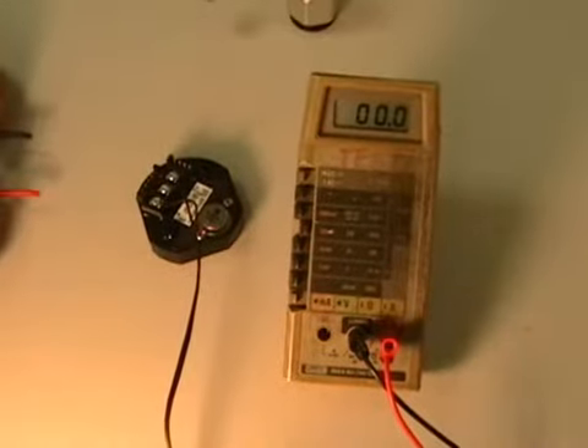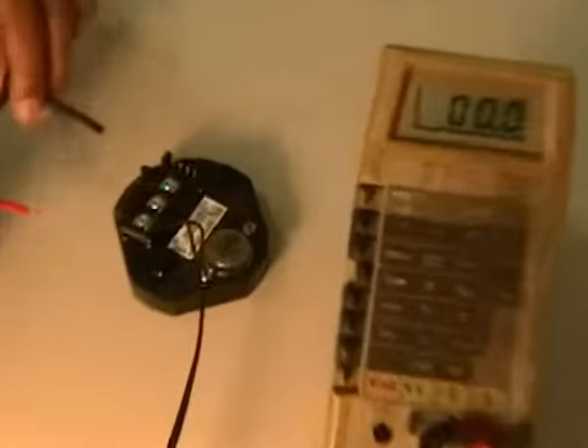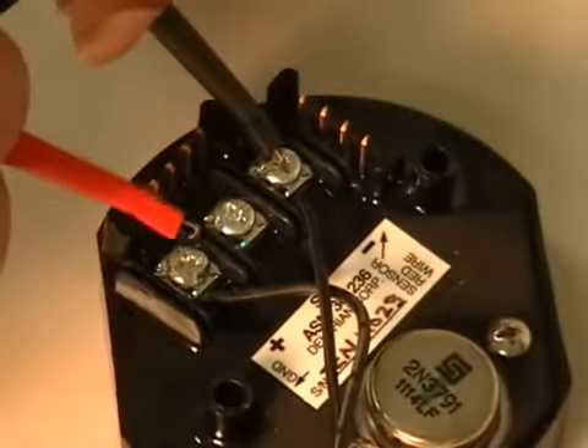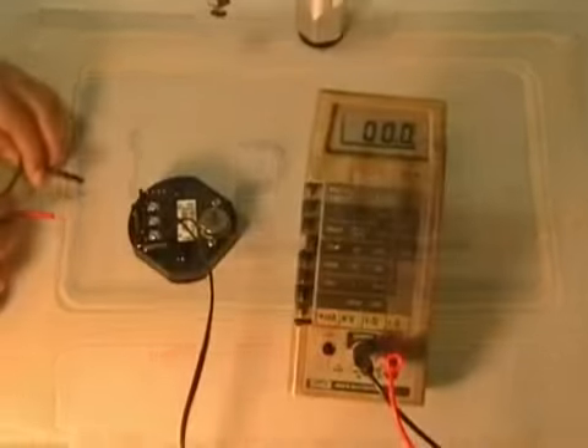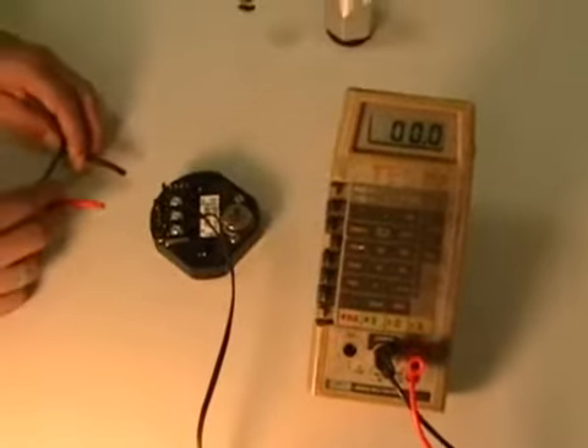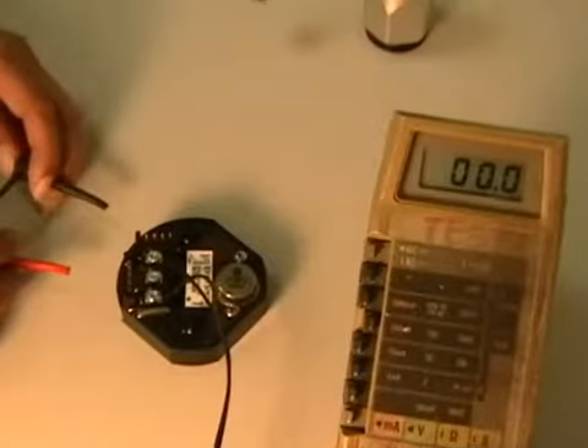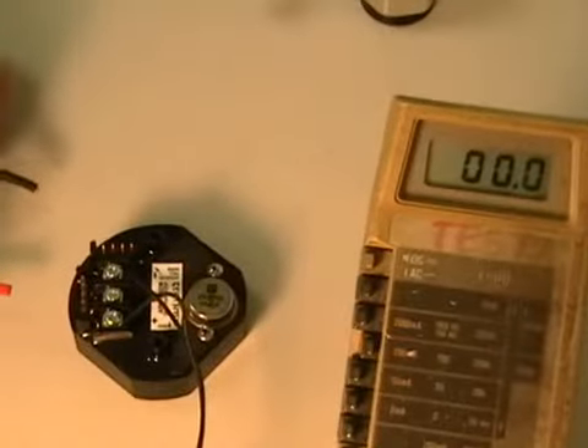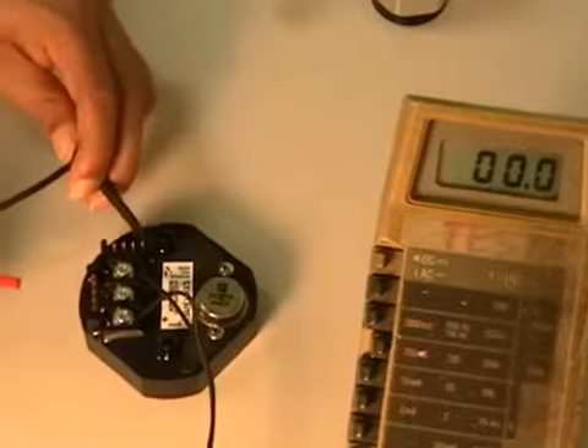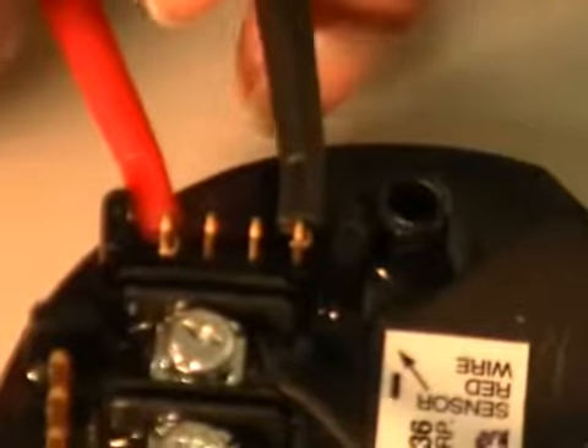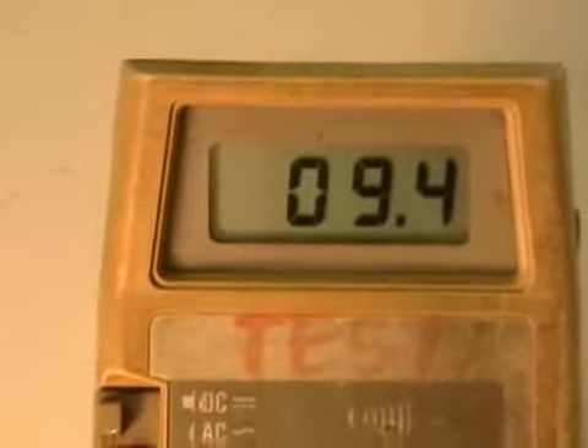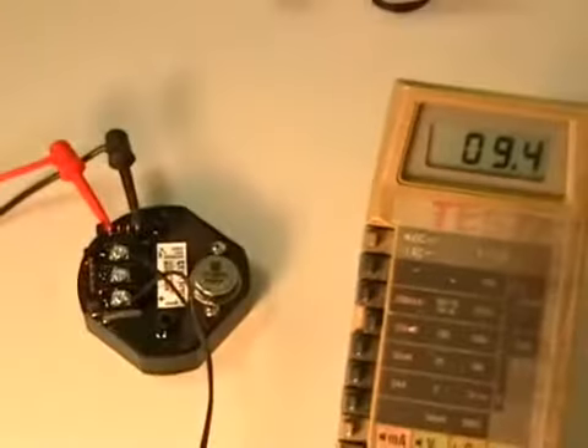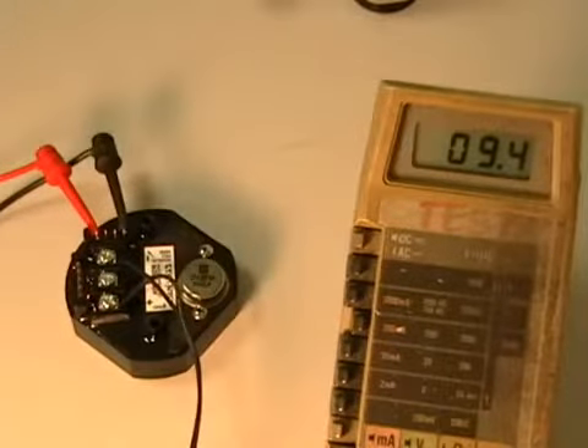The next several tests will verify if a transmitter is functioning correctly. With the DVM on volts and the transmitter powered, probe the plus and minus power terminals to verify 24 volt DC is supplied. Next, connect the test probes to the two outside pins of the 4-pin sensor header on the transmitter. This will verify its capability to operate the sensor elements at a specific voltage dictated by the coding resistor. The voltage should be approximately 9 to 10 volts.